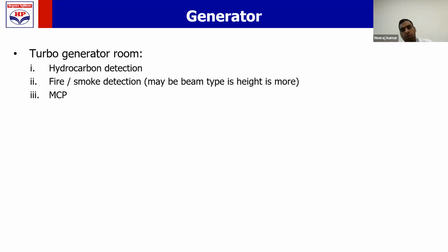Now we talked about what to do inside the generator. Now what you need to do in the generator room, the housing of the generator. Generators are generally not put in the open air; they are put in an industrial shed. That industrial shed, or the housing of the generator, shall be provided with hydrocarbon detection, fire and smoke detection, and manual call points. All three things shall be required: hydrocarbon, fire and smoke, and MCP.